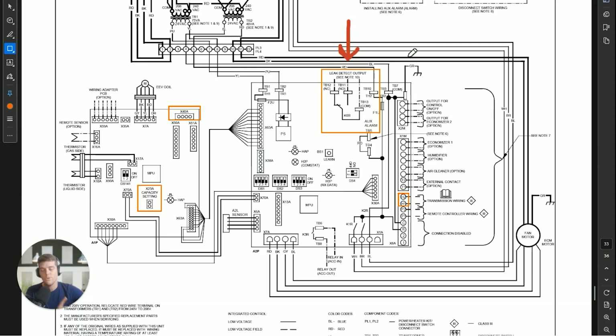Now, not every indoor unit has these additional sensors like this vertical fan coil does. You'll notice here that we've got a KRP relay built into this board here, which is kind of nice. Don't have to buy an accessory, although there is an accessory, which we'll show you here in a second. This is the leak detection terminals. As you notice, you have normally open, you have normally closed. I said those backwards because I'm dyslexic. And then you've got your common terminal wire.